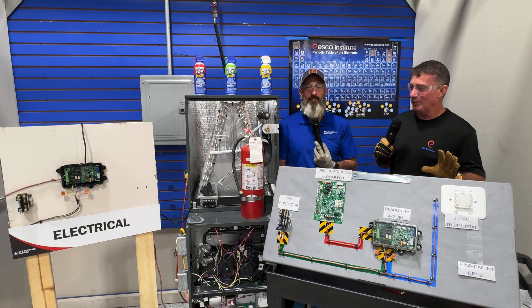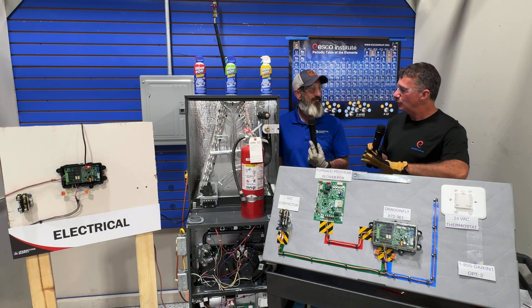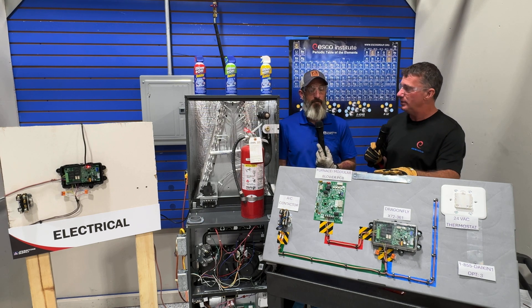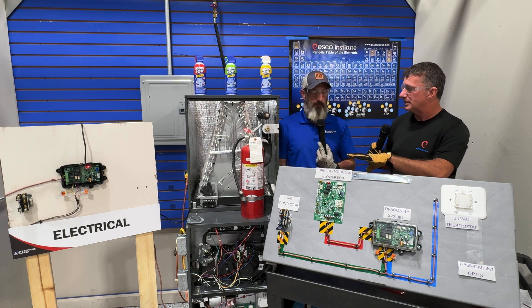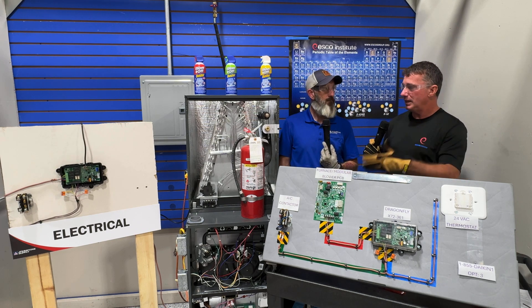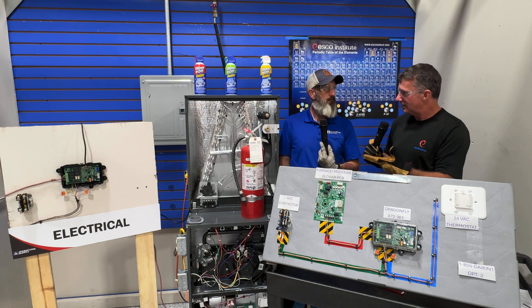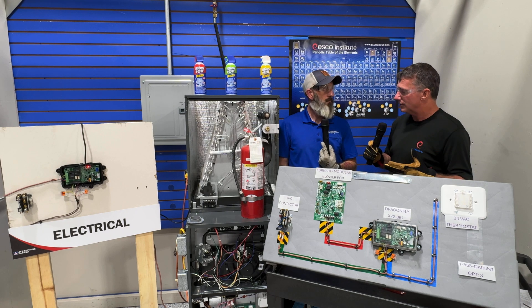All right everyone, thanks for joining us. I'm spending some time with Tom Robinson from the Johnstone Supply Grimme Group. Tom, how's it going? Doing good, man. Thank you for inviting me over. We're looking at some A2L refrigerant installation. You've done a fantastic job putting together an A2L mitigation training board. We actually have a live A2L mitigation system hooked up with a Daikin R32 system, and we're going to show what the mitigation control actually does once it detects enough refrigerant to go into mitigation. We keep talking about this but we've never actually seen what it's going to do.